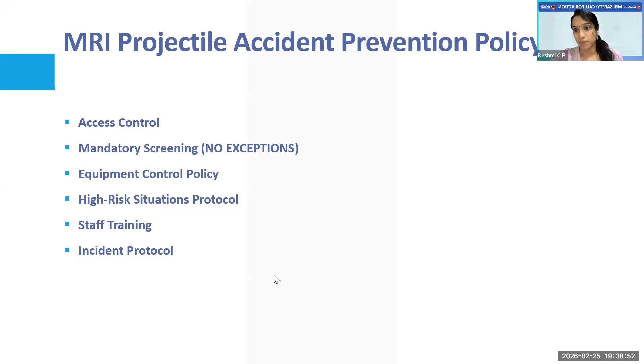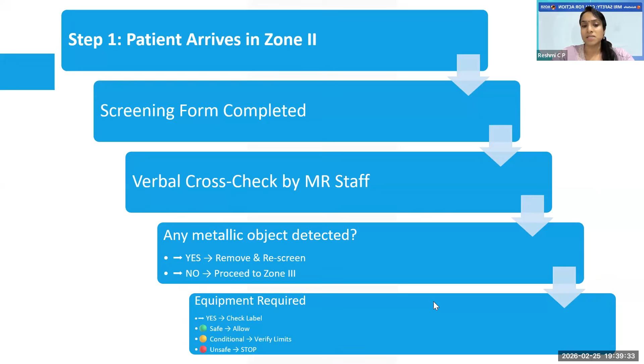We should follow the equipment control policy, that is, MR safe, unsafe, and conditional. We should also have a drill for high risk situations, especially if the patient collapses or suddenly has breathing difficulty. A proper policy should be in place. This is the step we follow in a hospital: if a patient arrives in zone 2, the screening form is completed and there is a final verbal cross-check by the level 2 MR personnel. If any metallic object is detected with the ferromagnetic detection system, it should be removed and the patient rescreened. If there is something abnormal, they have to go back to zone 1. If nothing is there, they can proceed. For equipment, MR safe is allowed, conditional means you have to see the limits, and unsafe is stopped.